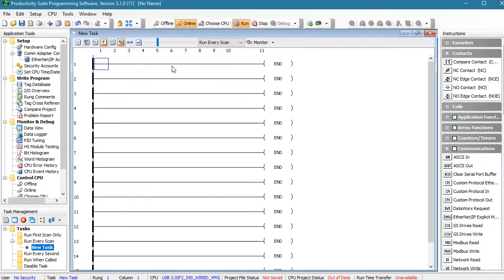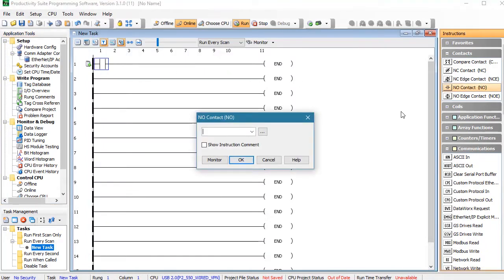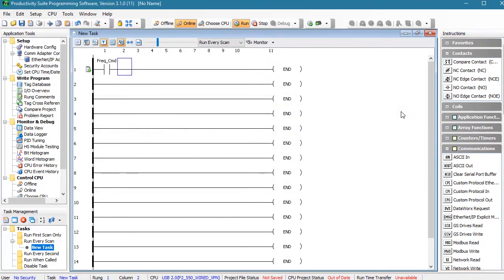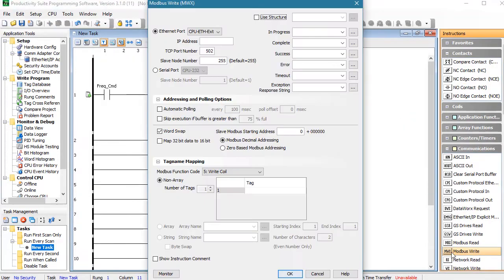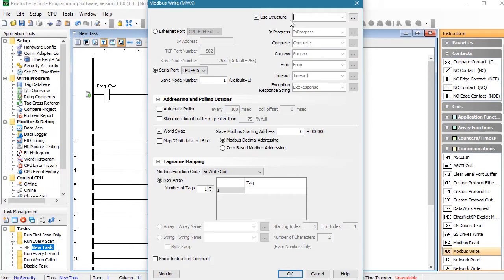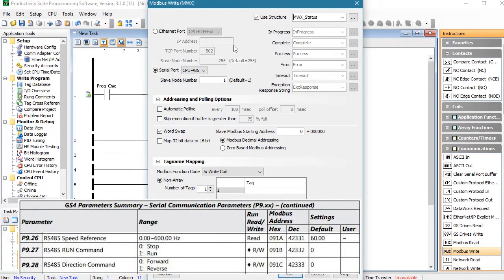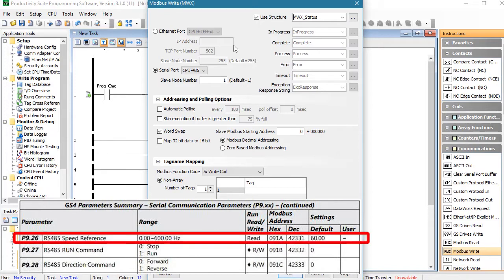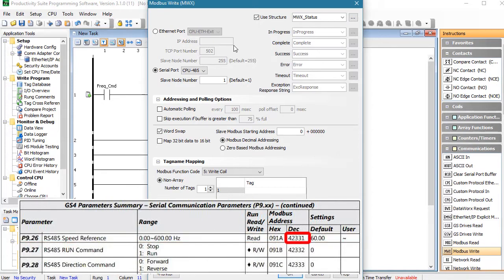Great, now we just start writing instructions. Let's create a contact to tell the drive to change speed, and we'll have that issue our Modbus write instruction. We are using the RS485 serial port. We want to talk to the GS4 drive at this node, and let's add a structure for error reporting. We see in the user manual that the RS485 Modbus RTU frequency command is at address 2331, so we put that here.